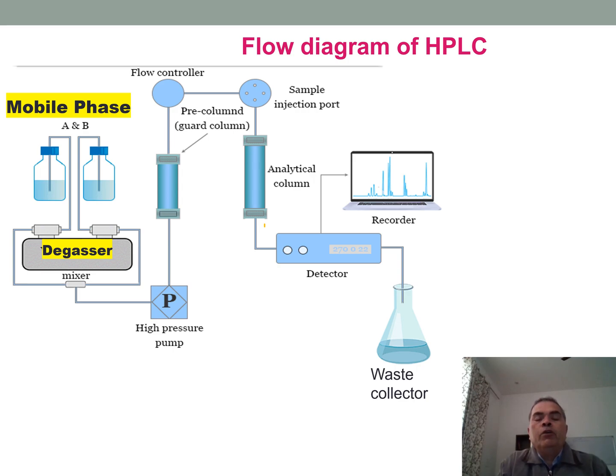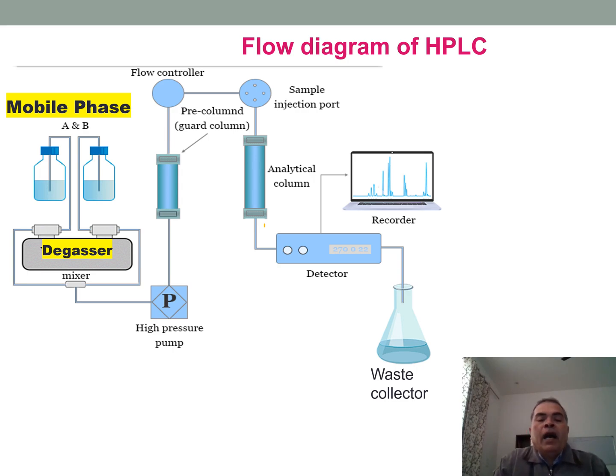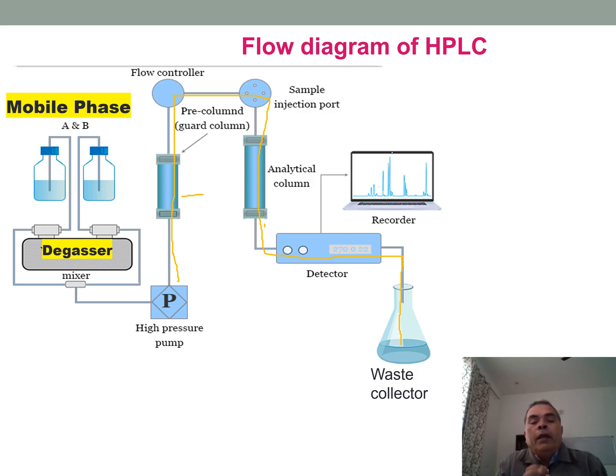Flow diagram: the mobile phase is a solvent or composition of different solvents. The mobile phase reservoir contains the mobile phase. The degasser removes dissolved gases from the mobile phase. The pump delivers the mobile phase at high pressure. It then flows to the guard column, then the flow controller, then the sample injection port, and then into the analytical column.